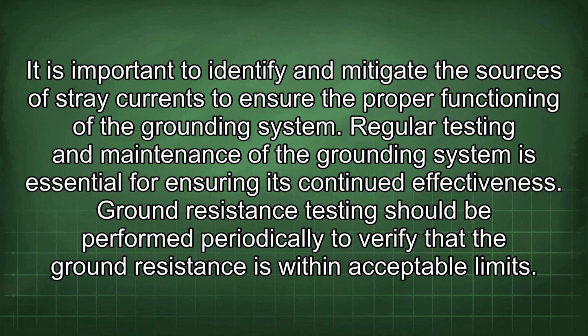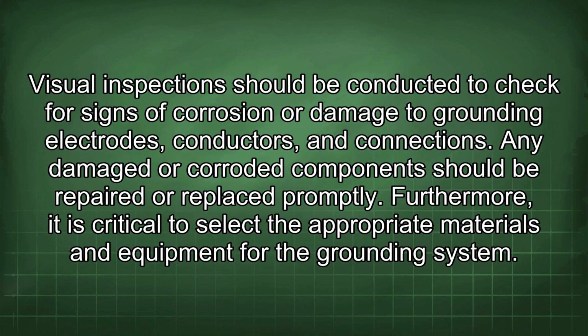It is important to identify and mitigate the sources of stray currents to ensure the proper functioning of the grounding system. Regular testing and maintenance of the grounding system is essential for ensuring its continued effectiveness. Ground resistance testing should be performed periodically to verify that the ground resistance is within acceptable limits. Visual inspections should be conducted to check for signs of corrosion or damage to grounding electrodes, conductors, and connections. Any damaged or corroded component should be repaired or replaced promptly.